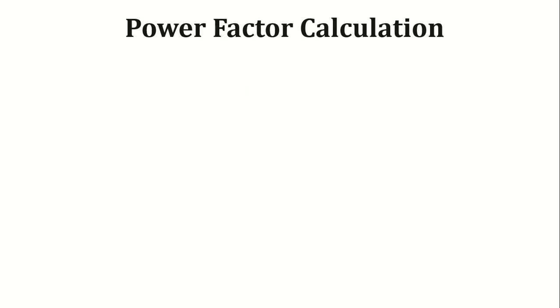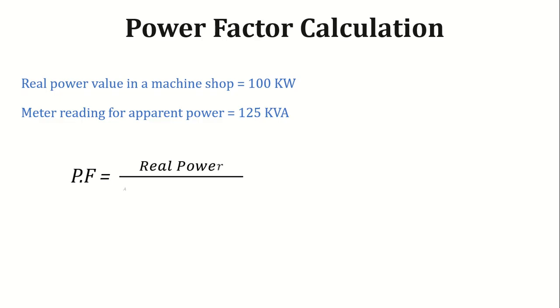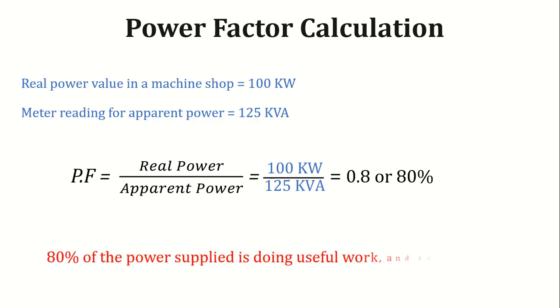To understand further, let's solve a simple numerical. We have a machine shop that uses 100 kW of real power, and the apparent power meter reads 125 kV amperes. Power factor equals 100 kW of real power divided by 125 kV amperes of apparent power. So the power factor is 0.8 or 80%. This means that 80% of the power supplied is doing useful work, and 20% is wasted.